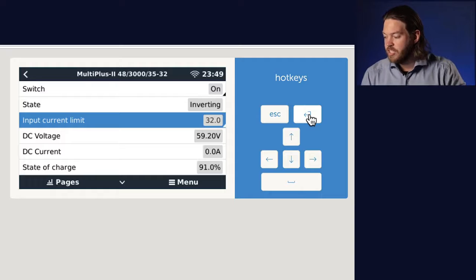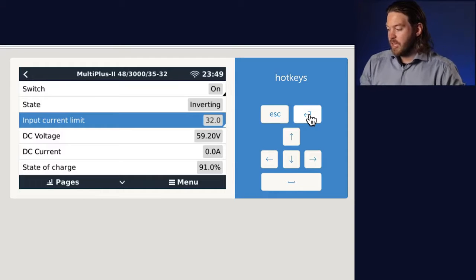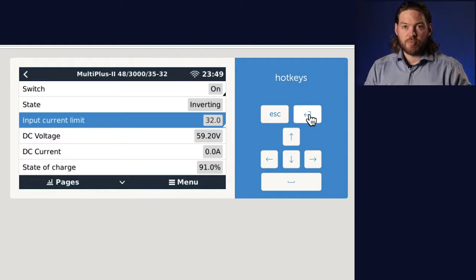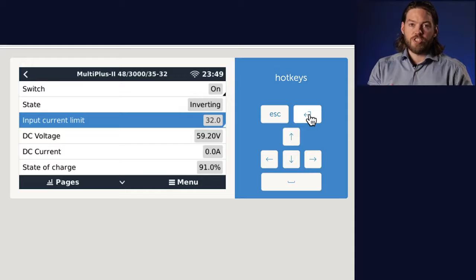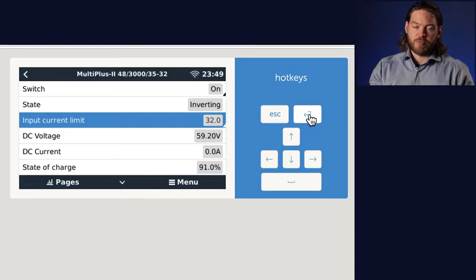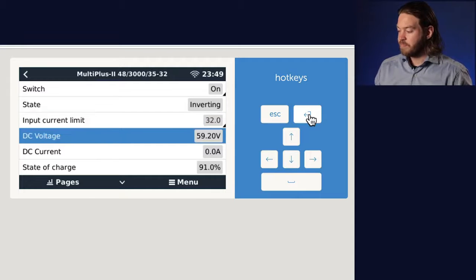Also important here to note is the input current limit. This is now combined, so this input current limit is for each unit, but each unit can produce that much power, so you have to sort of divide the total number here by 3, or multiply it by 3, depending on how you want to think about it. So if you only want to allow, let's say, 30 amps in, you'd set this to 10 amps, because each unit will allow 10 amps in, and that'll allow a 30 amp connection in, if all units are connected to the AC input.